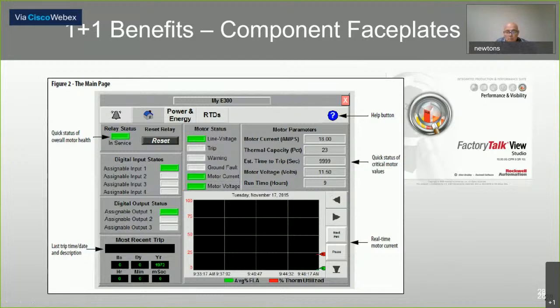Another benefit of the Premier integration is the visualization side. Here you can see there's a pre-configured, what we call a faceplate, with a number of parameters and status information. This is actually an E300, an intelligent overload, and basically all that information that's seen there is available to us. And this is a quick container. Again, it's pre-built with just one connection into the tag database, it can bring forward all this information, analog and discrete, and this graphic can be used at an operator interface level, or at a higher level on an HMI, which obviously means there's a good level of consistency of graphical representation across a site.